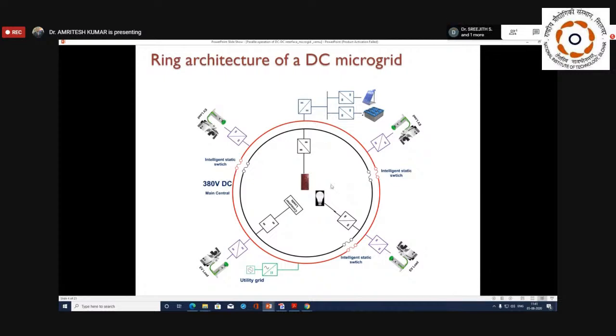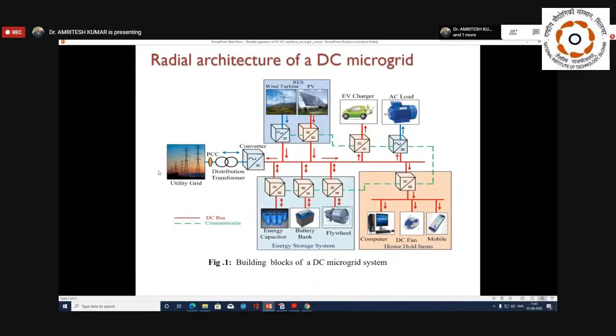For 380 volt DC grid and 48 volt DC grid. Basically, 380 volt is being kept as a standard. The reason is that a single phase can be integrated easily at this 380 volt via your power electronics converter. So basically, you can see in a radial architecture, this converter, if it is connected with the single phase line like 230 volt, then it can easily connect with the 380 volt DC bus. So this is the standard.